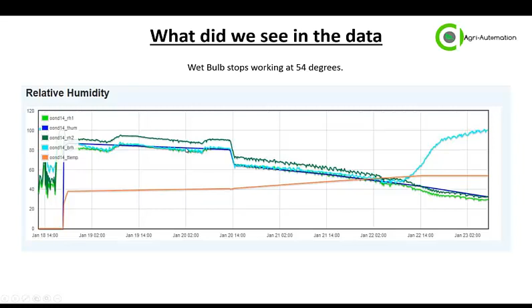We can use the relative humidity control during the ordering or damping phase. So once the tobacco is dried, you need to put the humidity, the moisture, back into the leaf so you can actually work with it. So here you can see, opening the solenoid valve, the water will start blowing into the dryer, and the humidity will then start building up until it hits the target, and then the controller will make sure that it doesn't go over the target that you've set. That basically reduces mildew in the grading room.